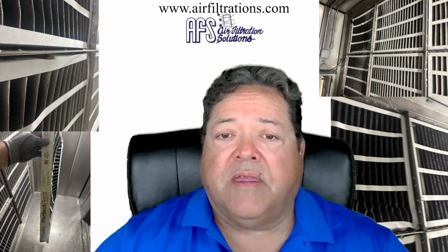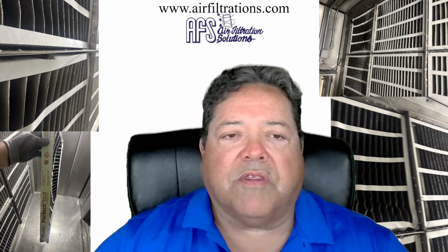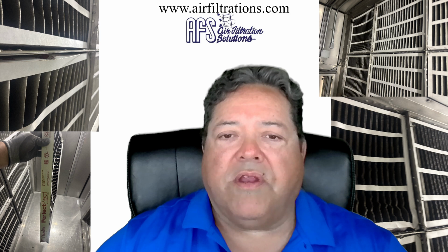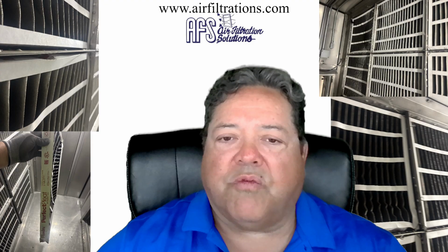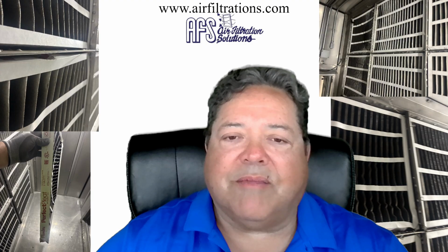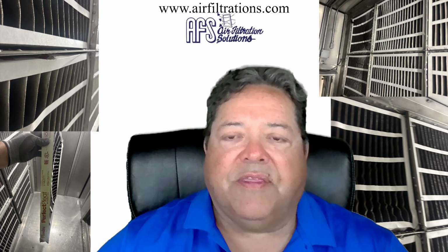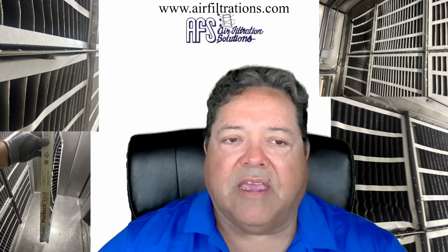So fortunately, the engineers here, this is about the fifth, sixth air handler that they've replaced within the last several years. And once it was turned over to us, we've always pointed out the pleated filters and showed the engineers, if anything, maybe you could recommend to the contractors that you don't want pleated filters or cardboard frame filters. But that ends up becoming just a headache to debate. So what these guys do is, immediately when the air handler is turned over to engineering, they let us know so we could get in there, take out the pleated filters, and put in our MERV 11 PolyShield fiber bond panels in place.